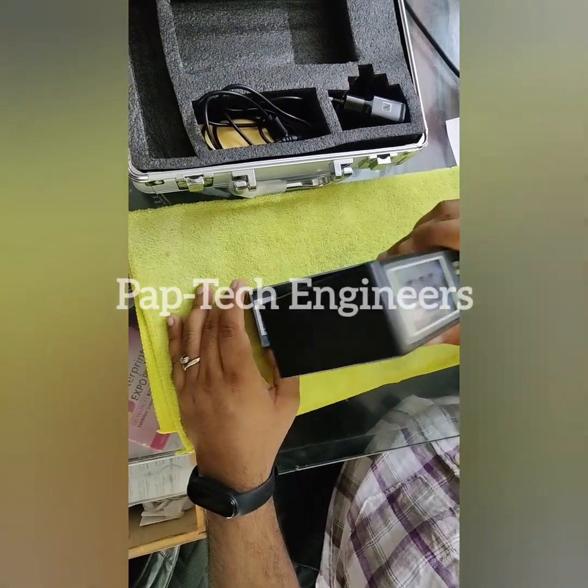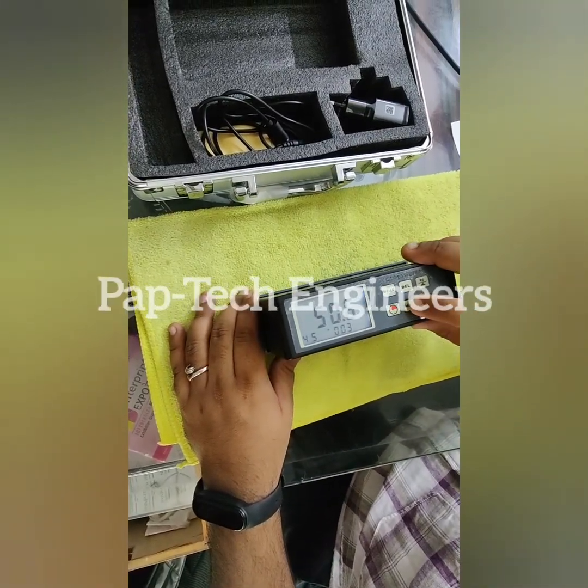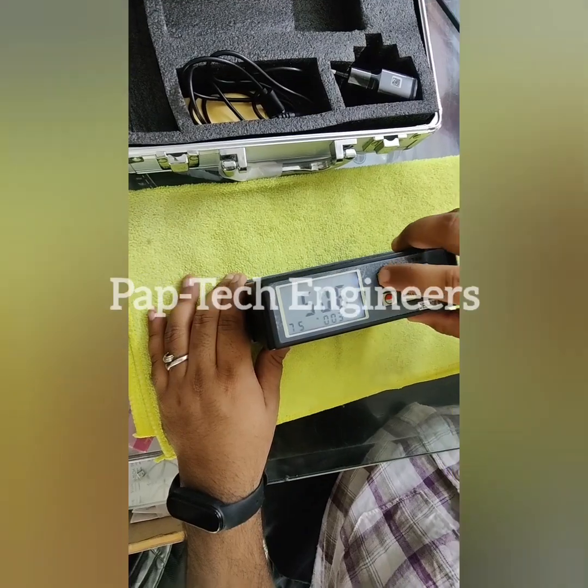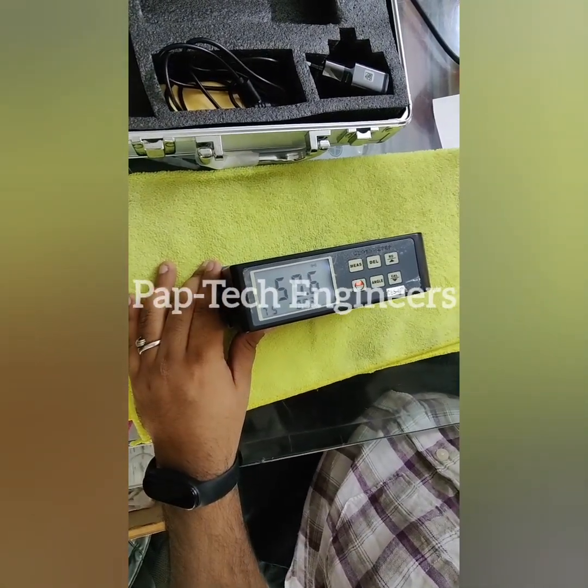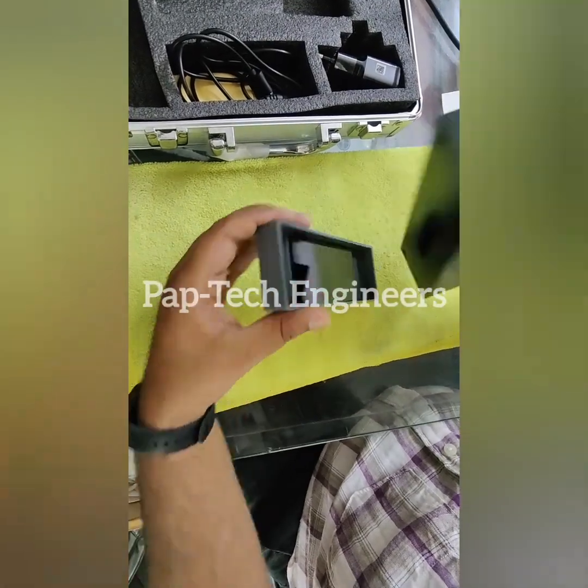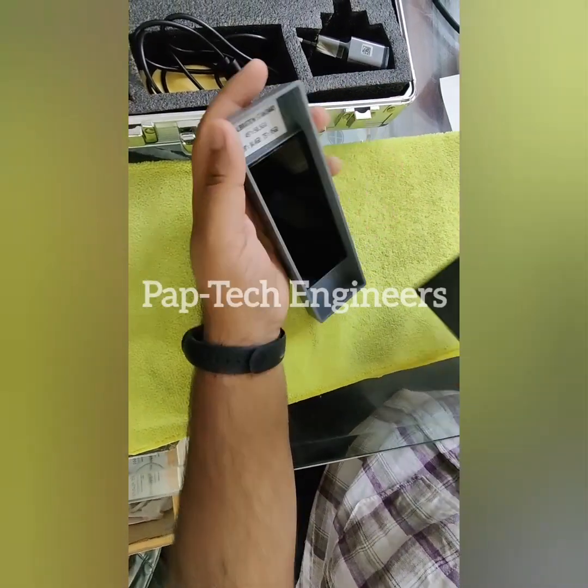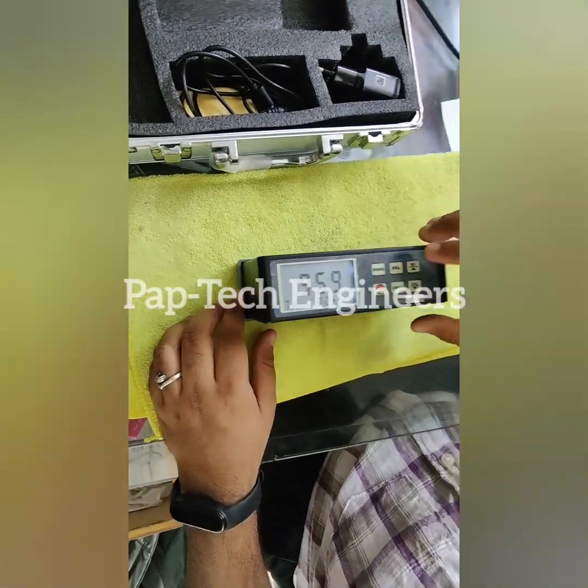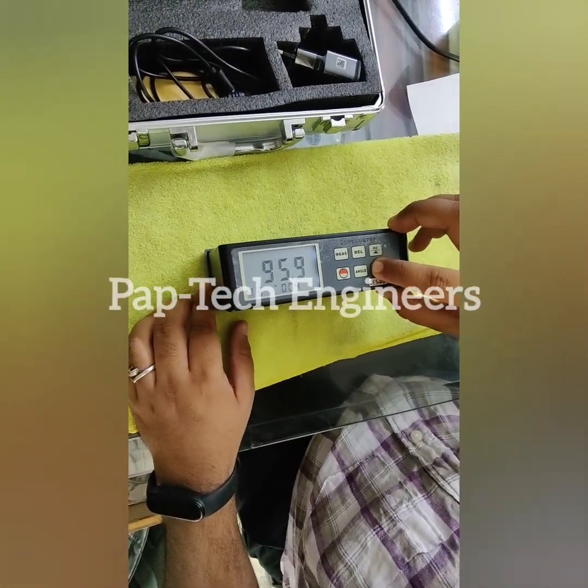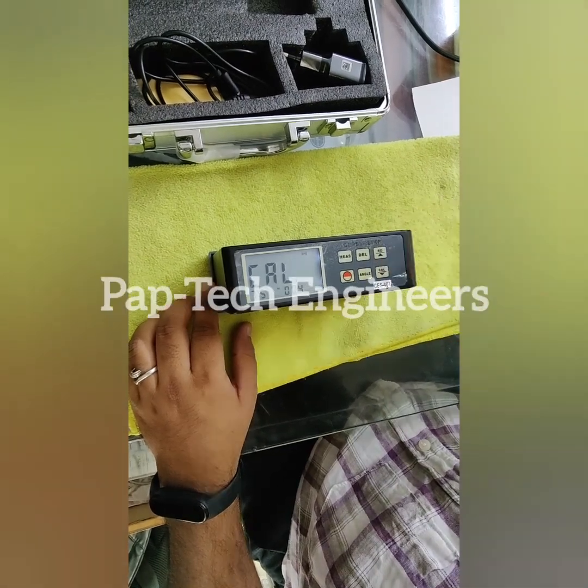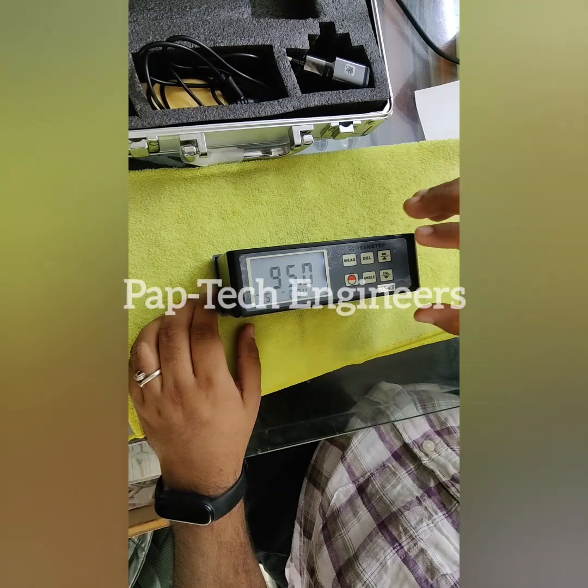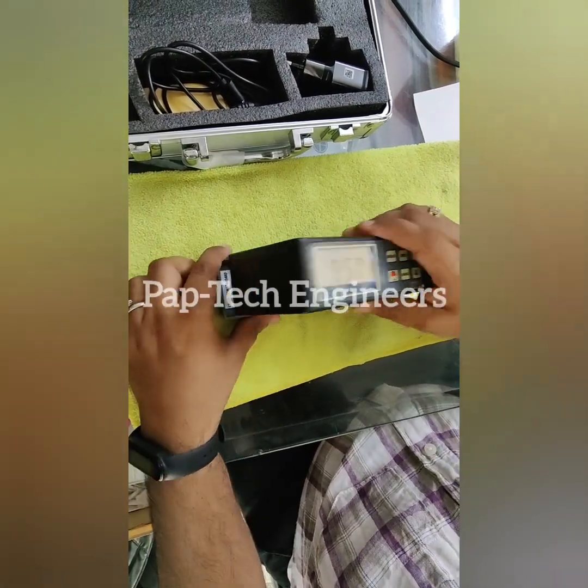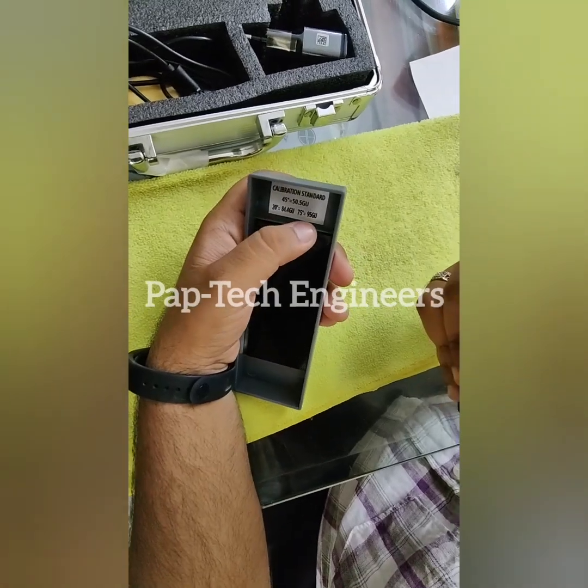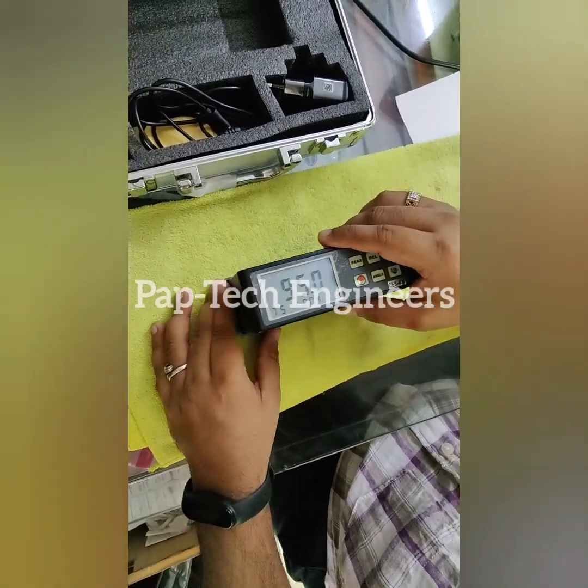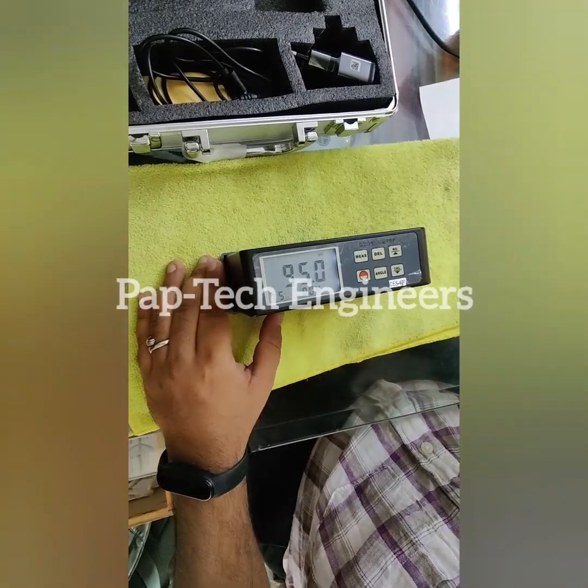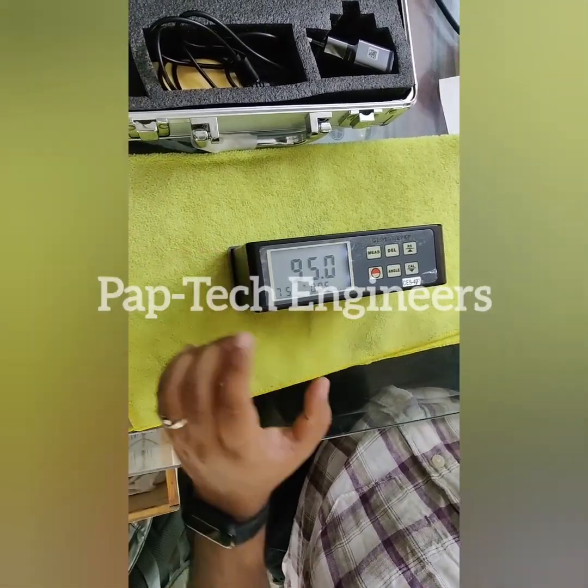Now let's check on the 75 degree. To change the angle, we use this angle button. Now again the measurement button. As you can see, 95.9, and the standard reading is 95. It means there is a big gap. So let's press the calibration button and make it more calibrated at this 75 degree angle. On different angles we have to calibrate it. So as you can see now, it's coming 95, and the calibration standard is 95. It means the machine is now calibrated at 75 degree angle. Again we can check with this measurement button, and we'll get the same reading.